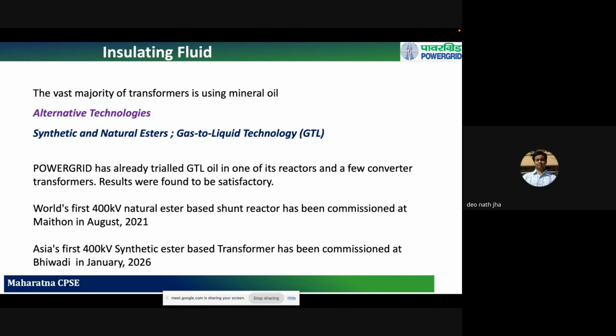So the advantage of these oils with respect to mineral oil is that they have very high fire point and flash point. Earlier I talked about the temperature going high and the transformer failing. Mineral oil catches fire once the temperature reaches about 160 degrees inside the transformer. But these synthetic and natural esters have fire resistance up to 300 degrees centigrade. So till 300 centigrade, there will be no fire in the transformer.